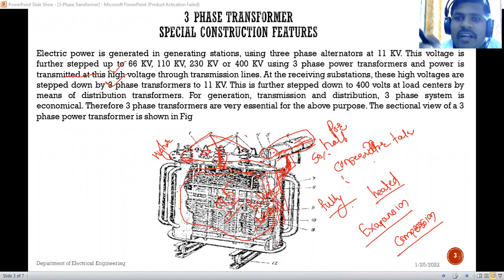त्याच्यामध्ये जे काय half filled oil असेल ते ट्रान्सफॉर्मरच्या मेन टँक मध्ये जाईल. So the main tank oil requirement should be fulfilled, right? So that means this is used for protection purpose, and also for the function of oil expansion and compression, the conservator tank is useful. Getting this point?